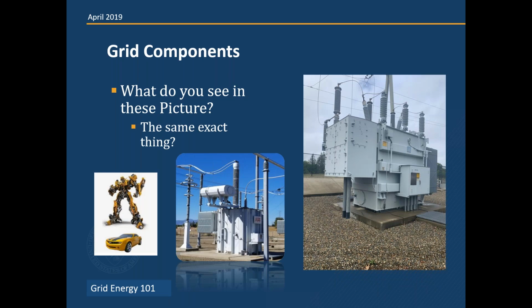So what am I seeing here? I see the same exact thing. Let's start on the left. Yes, that is a yellow Camaro, and it's a transformer. It's Bumblebee. It's a transformer, but not the type of transformer that I'm talking about. In the example in the middle there, we have a 500 kV line reactor that looks like a transformer, but its purpose as a reactor, as I said a few slides ago, was, if you put a reactor in, it lowers the voltage. If you remove the reactor from service, it raises the voltage. And then on the right is your traditional 115 kV, stepping it down to 12 kV transformer. Next slide, please.